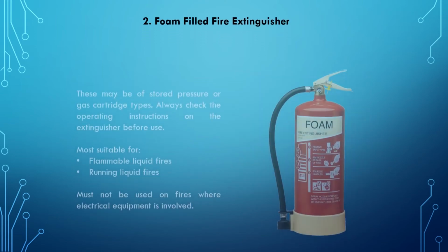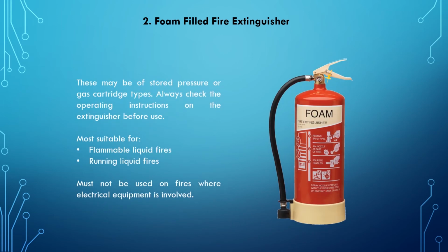Foam-filled fire extinguisher. These may be of stored pressure or gas cartridge types. Always check the operating instructions on the extinguisher before use. Most suitable for flammable liquid fires, running liquid fires. Must not be used on fires where electrical equipment is involved.